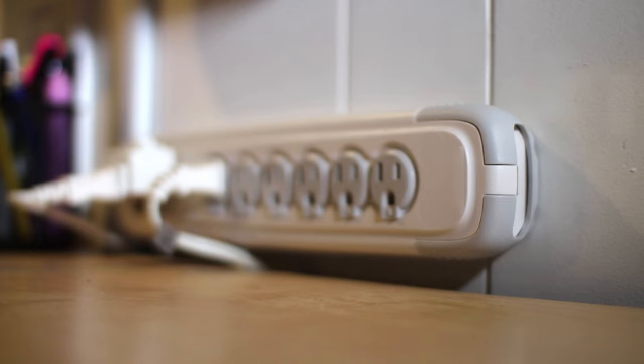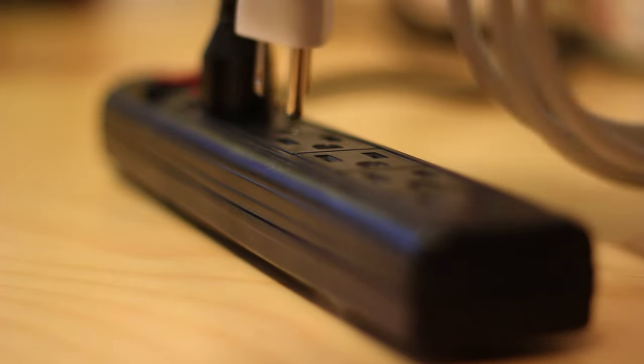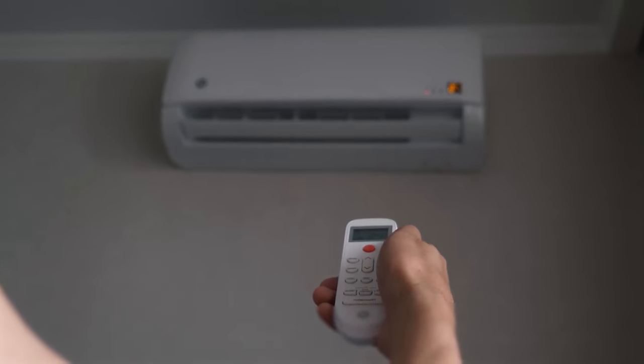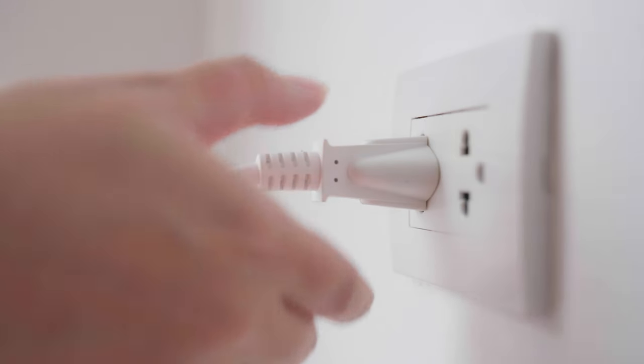You've probably noticed we've been comparing 8,000 BTU systems throughout. That's because 8,000 BTU per hour is nearing the maximum electrical load a 15-amp household 120-volt circuit can handle — meaning a more powerful system would consume too much power for your circuit and probably trip breakers. But since mini splits are so much more efficient, you can get higher cooling capacity on the same electrical circuit. Because of this, the most common size you'll see for mini splits is 12,000 BTUs per hour on a 120-volt electrical circuit.